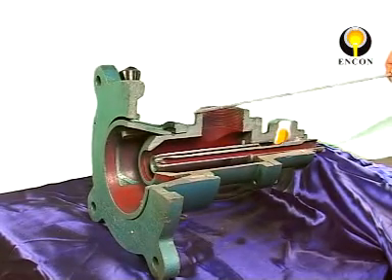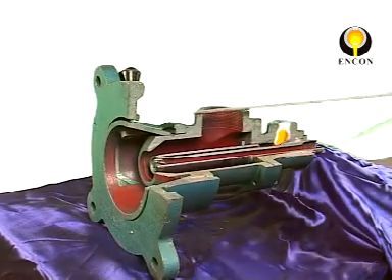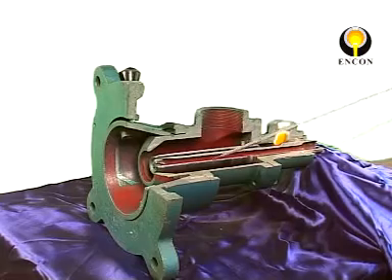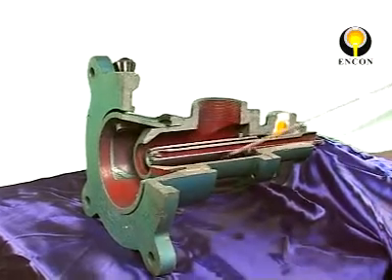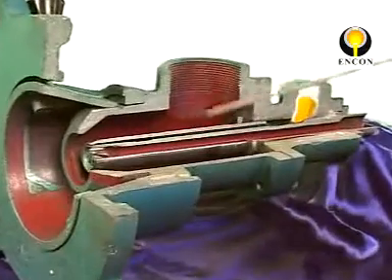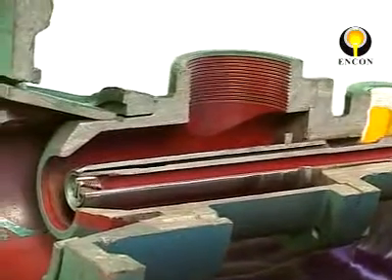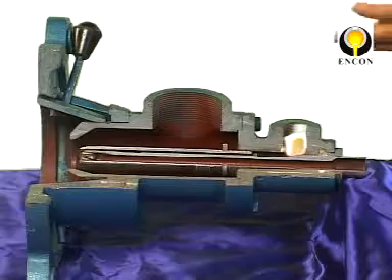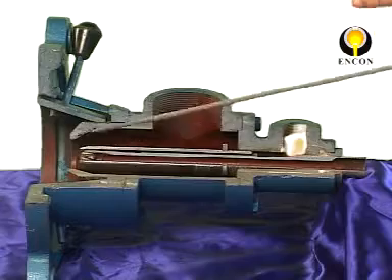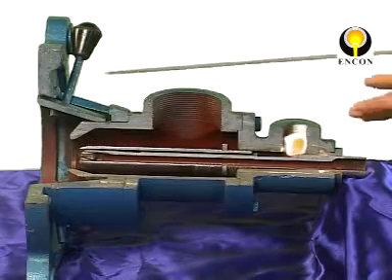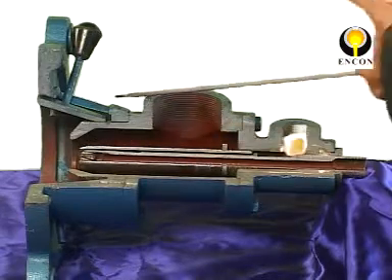This burner can take up to 300 degrees of preheated air and because the tubes are all made of stainless steel, the life of the burner is very large. So basically it has minimum maintenance, it has the advantage of fuel saving and normally a burner system pays back in a couple of months.